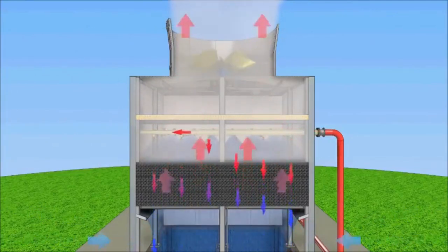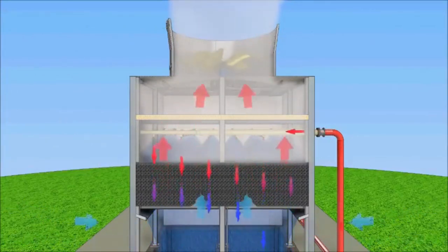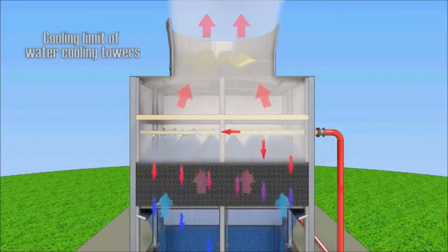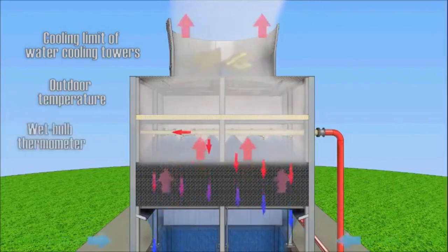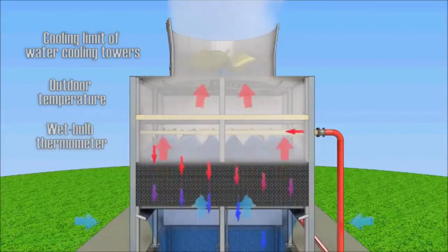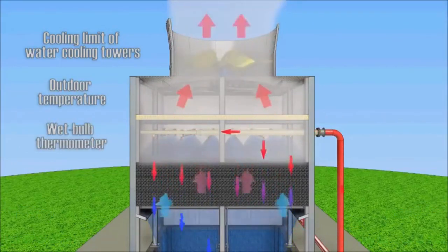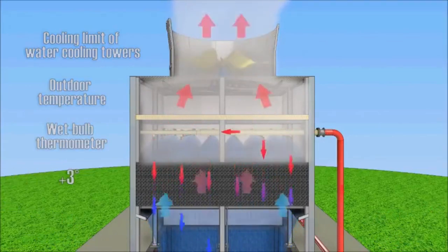Theoretically, the ideal limit of cooling water in the cooling tower is the temperature of the outside air wet bulb temperature. In practice, the limit of cooling is the temperature of the wet bulb thermometer plus 3 degrees Celsius.